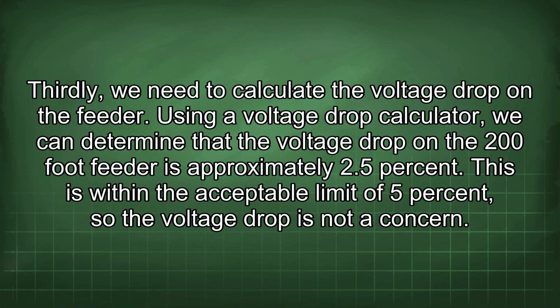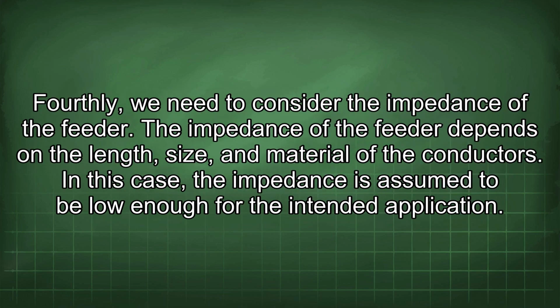Thirdly, we need to calculate the voltage drop on the feeder. Using a voltage drop calculator, we can determine that the voltage drop on the 200-foot feeder is approximately 2.5%. This is within the acceptable limit of 5%, so the voltage drop is not a concern. Fourthly, we need to consider the impedance of the feeder. The impedance of the feeder depends on the length, size, and material of the conductors. In this case, the impedance is assumed to be low enough for the intended application.